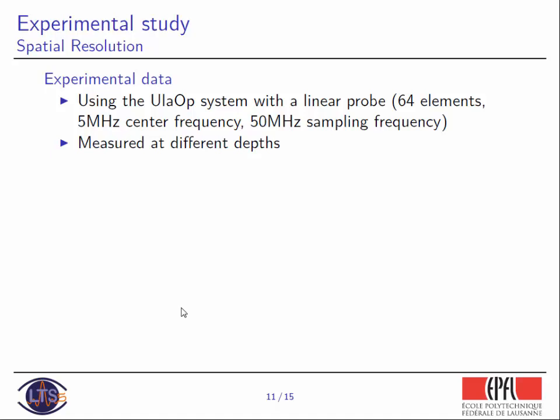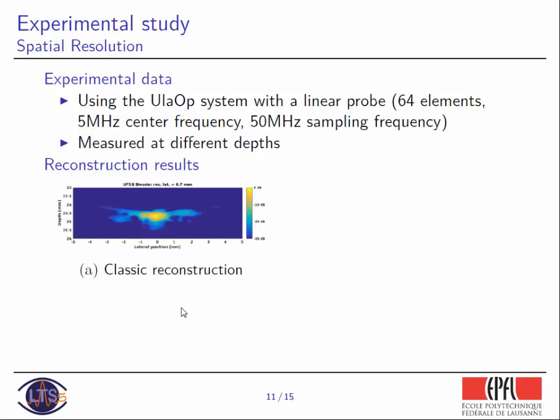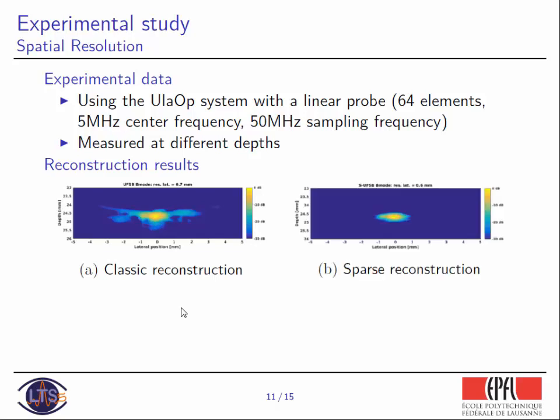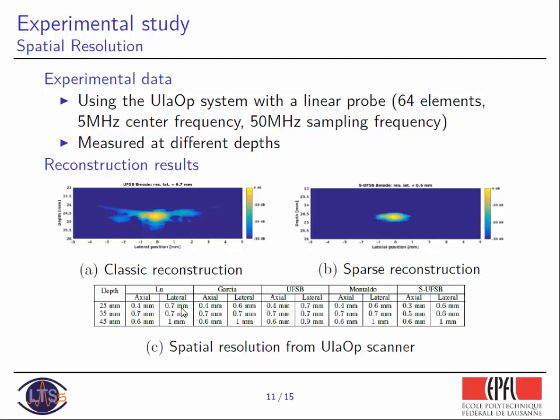What about resolution? To measure resolution, we used the same probe setup — 64 elements, five megahertz center frequency, 50 megahertz sampling frequency. We measured resolution at different depths, placing a wire at 25 millimeters, 35 millimeters, and 45 millimeters, then applied the same reconstruction methods. With our method, we clean the image somewhat, but when we calculate the resolution, we did not see a real increase — the main lobe remains the same as with other methods. Why? Because we promote sparsity not in a Dirac basis, which would promote point-like spikes, but in a wavelet-type basis that promotes more structure.